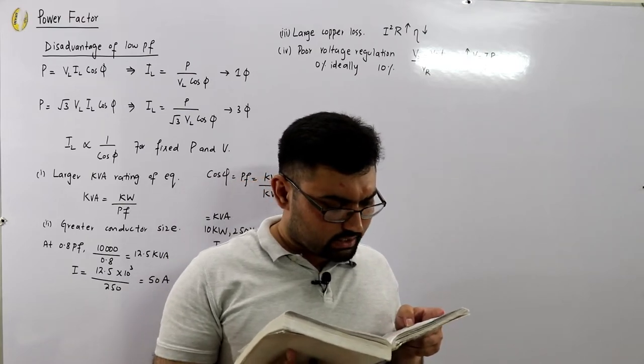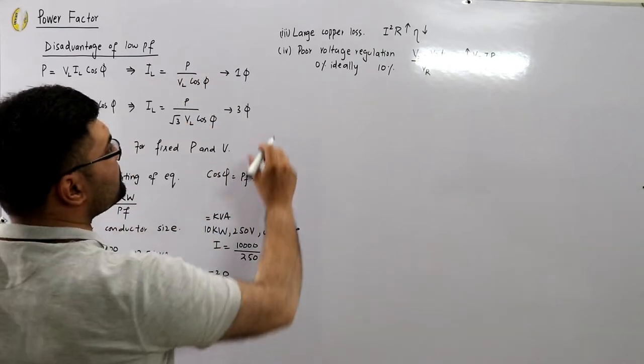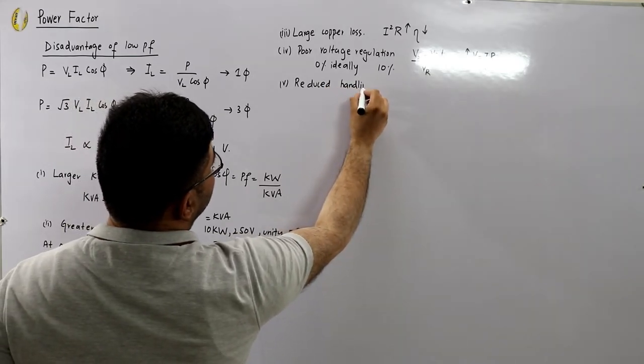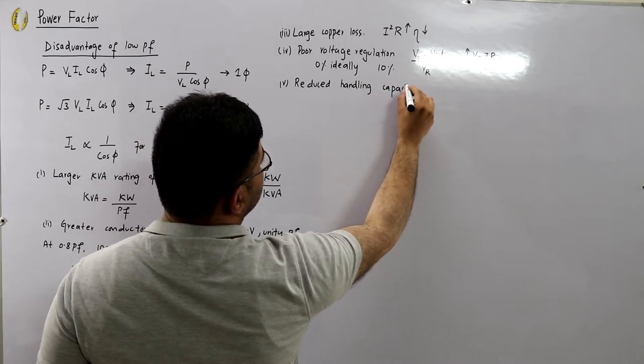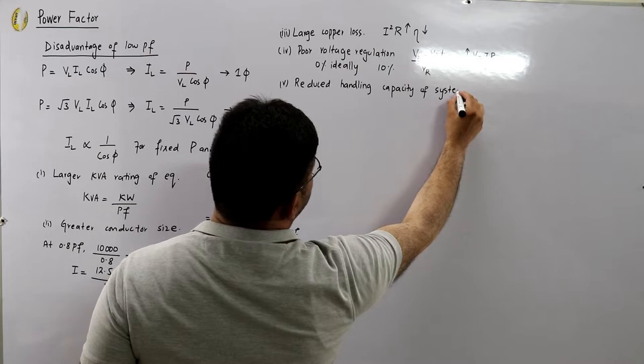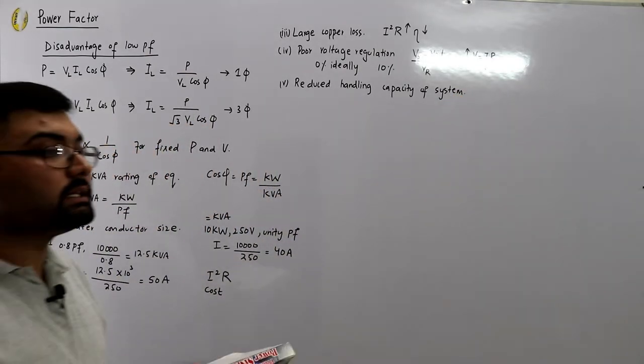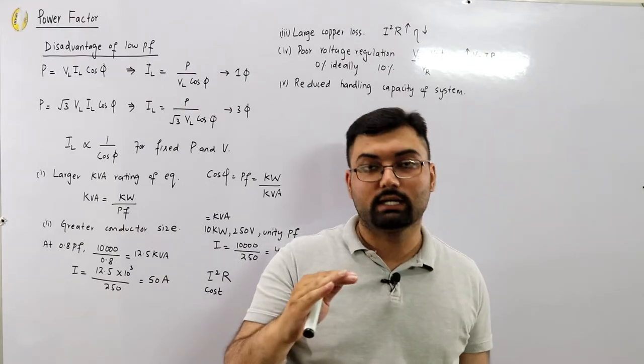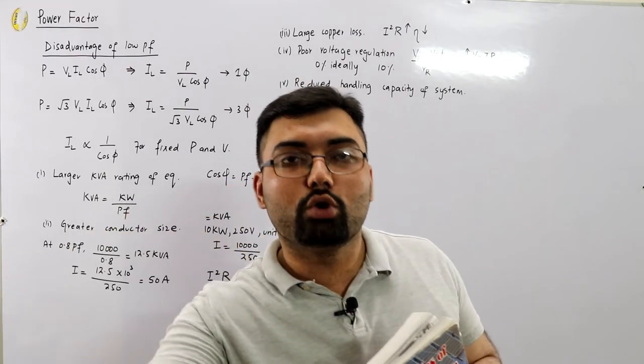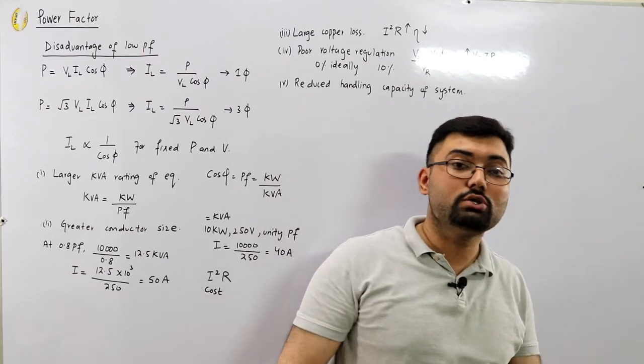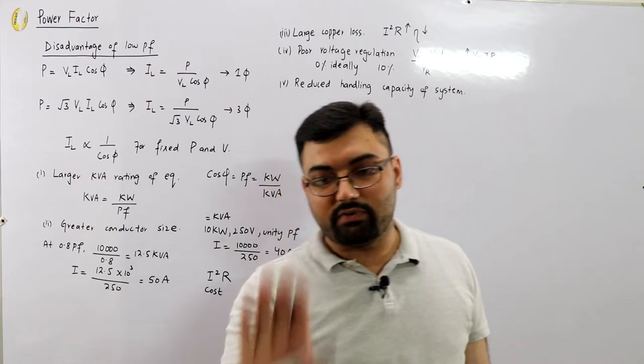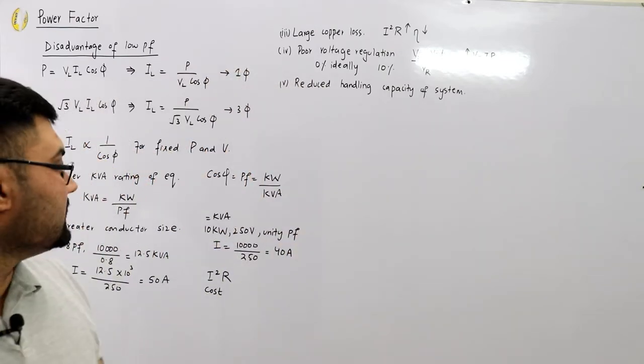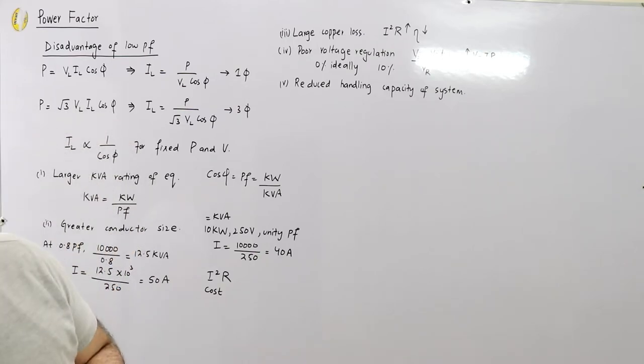The fifth disadvantage is reduced handling capacity of the system. At a lower power factor, equipment is not fully utilized because the load demand does not approximate the KVA rating of the equipment. At a higher power factor, you utilize the equipment's full rating.